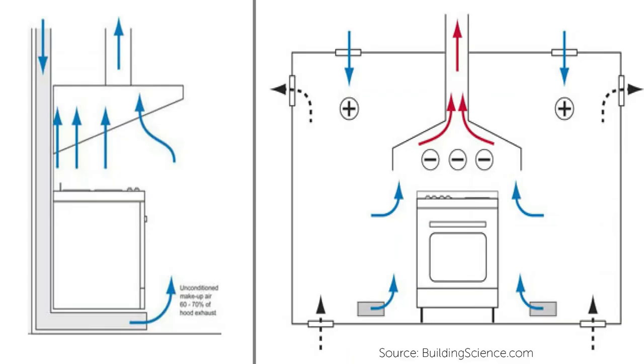In tight homes, makeup air may be needed to offset the depressurization created by the range hood with as little as 200 CFM in exhaust. In any home, a range hood moving 400 CFM or more requires makeup air. Makeup air is ideally provided through a supply ducted to the kitchen, but not to the range hood directly, in order to avoid bypassing and to allow for effective mixing of the air.